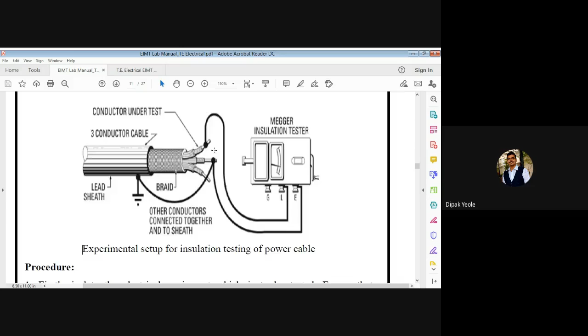We use this for measurement of insulation resistance. The L terminal is connected to the conductor of the power cable — you understand now the power cable's conductor is connected to which terminal? The L terminal, the line terminal. And E is connected to the body of this power cable. This is the experimental setup for insulation testing of power cable.